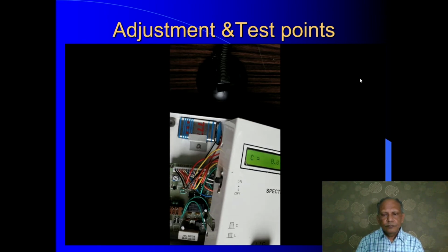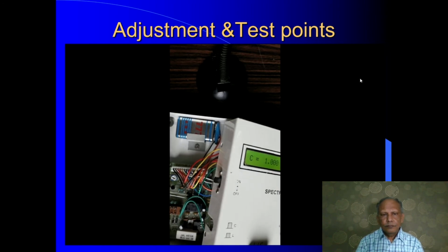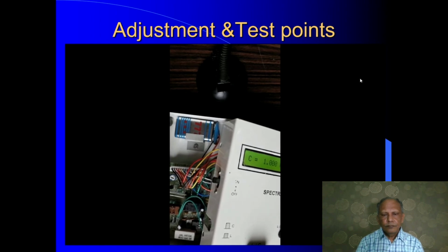Now there is one more, LK2. Once we short this, it will show the operation of the relay, and also it will show the value of the internal standard capacitor. Now I am shorting LK2. It is showing 1000 PF exactly, and also the sound of the internal calibration relay can be heard.